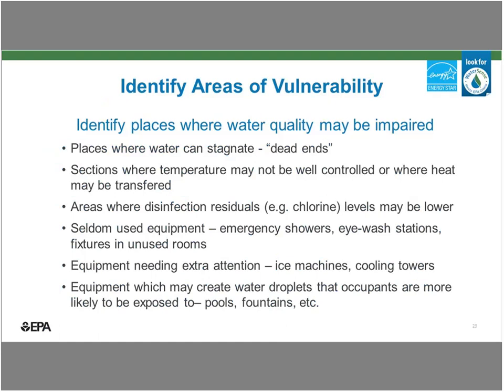Legionella thrives in certain temperature ranges and when there isn't enough disinfectant left in the water. You want to look at where water may not be flowing continuously, such as a dead end or a part of the facility where water isn't being used, and also sections where temperature may not be well controlled or where heat may be transferred to it. Legionella thrives within a certain temperature range, so you want to keep your water hotter than that or really cold, not in the warm middle range where bacteria thrives.